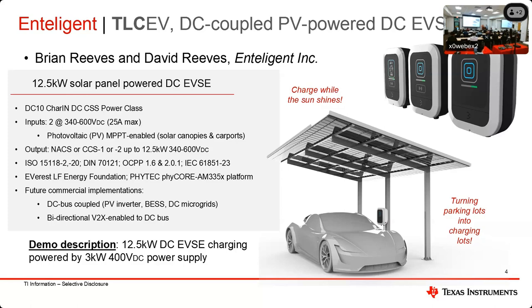The AC in here, they might not have a microgrid. My question is actually around how well does your device respond to that microgrid controller? We have developed a protocol over Modbus and CAN bus. It's based on a SunSpec DER communication model, which fits in with that whole ecosystem, so we can plug into an inverter or an energy management system. It's based off of a battery model, but somewhat modified. We have that protocol and an SDK that we make available to our partners, and they have no problems with the integration in terms of how you can communicate back and forth.